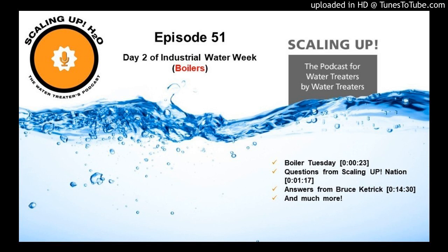The two things we can do is we can wet store it, which means we're going to completely purge the boiler of all of the air. So we're going to fill the boiler up all the way up into the steam header, right at the steam header, and that's going to be with heavily treated water, so we don't have to worry about corrosion taking place within that water.